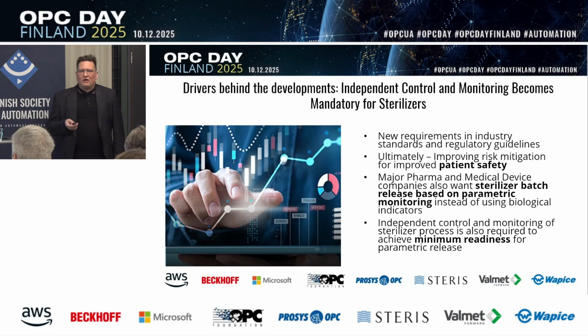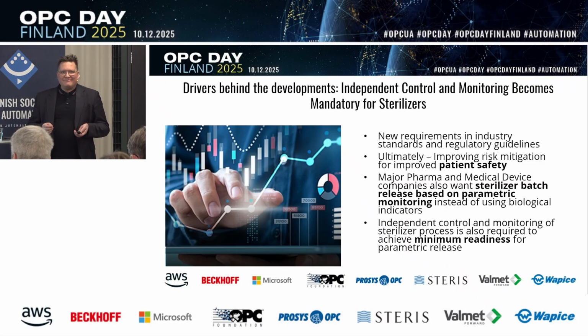When we're talking about sterilization processes, especially terminal sterilization processes for finished goods, one of the key factors for proving that your batch has been sterilized is a biological indicator. You're relying on a biological organism that you're killing in a process challenge device, many of which are located in the sterilizer load—more in a bigger chamber, a little less in a smaller chamber. You're looking at a biological organism that you're using for release, one of the main release criteria of a batch.